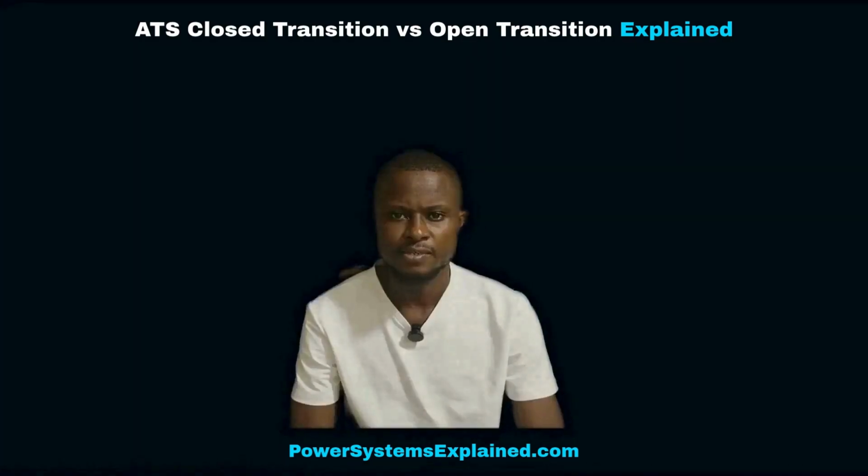The generator kicks in. The transfer switch does its job. Power is back. Then 30 seconds later, a motor trips. Control panel resets. Someone asks, what just happened? Because on paper, everything worked. This is the mistake I see more than almost any other on site.